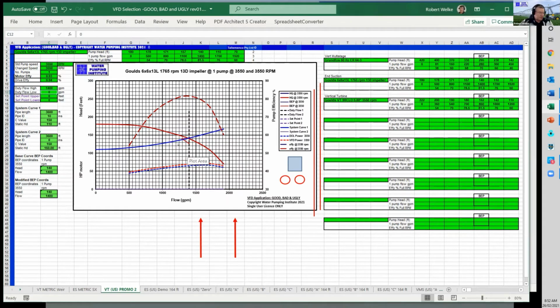We've got a duty head of 140 feet. We're going to modulate this VFD to run the pump at 1400 gallons a minute down to 70 feet head. So there's our other indicator: two horizontal indicators here, one at 140 feet and one at 70 feet. What is the pump horsepower at 140 feet head? If you follow this line down, it's the blue curve on DOL. It's 65 horsepower.